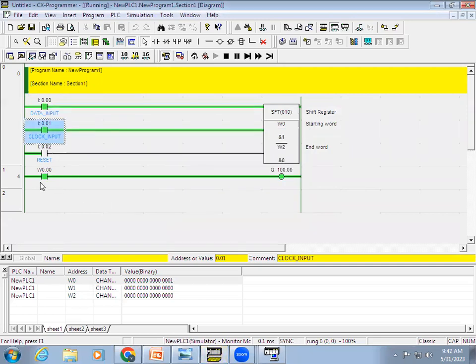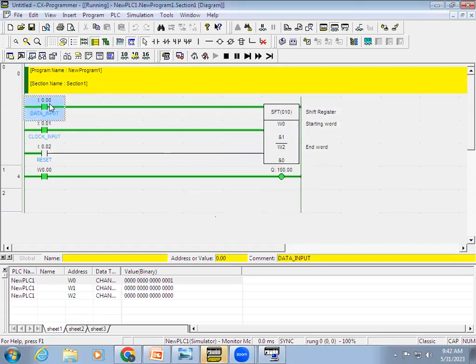What happened is that the data input's true status was moved to bit 0, so W0.0 is activated. Now the data input is off and the clock input is off. When the clock input is activated again, the current data input status is zero, so that zero will be given to bit 0. Whatever true status was present in bit 0 then shifts to the first bit.